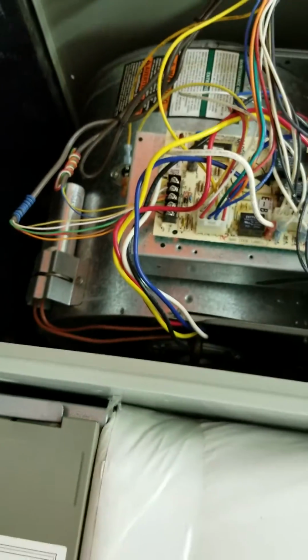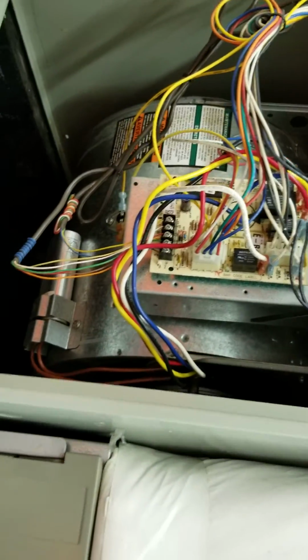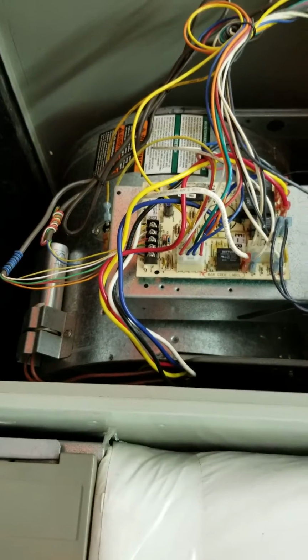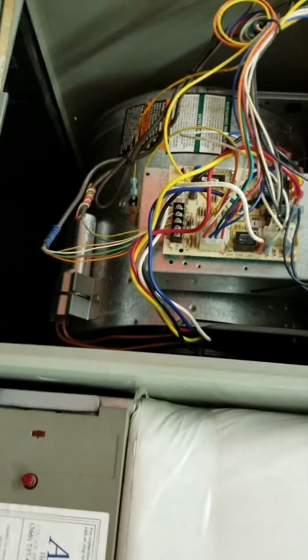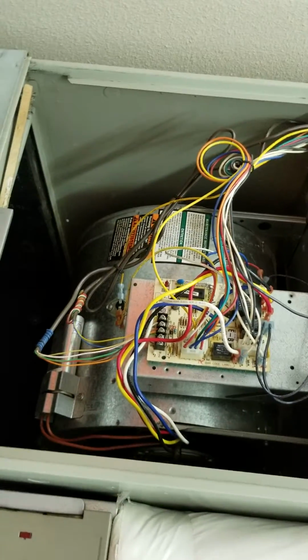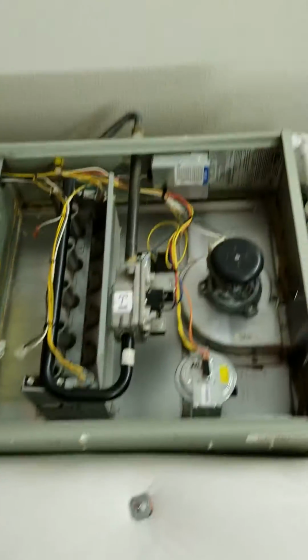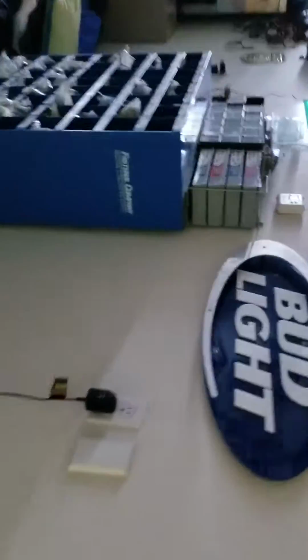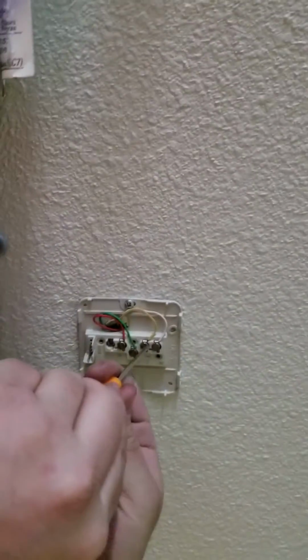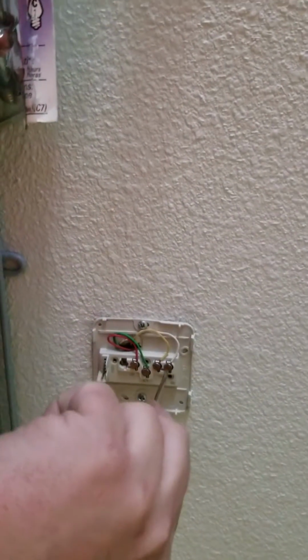Okay, because most failures can eventually be attributed to a loose wiring connection. Next thing we're going to do is do the same thing at our furnace thermostat. So grab your little screwdriver there, and we'll come over to the thermostat in this one. Okay, in this case, go ahead and remove the thermostat carefully in the wall, pull straight out, and make sure that the connections are tight.